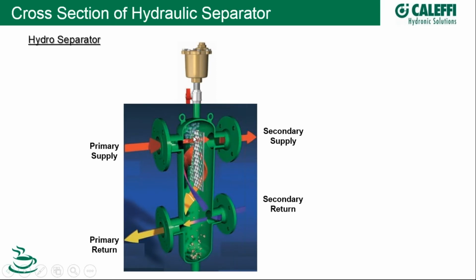Now these baffle plates have a little bit of perforation in them. You see these little holes perforated in them. This gives us a little bit of what's called coalescing, and you can see air bubbles that are actually coalescing out and up through the air vent. We'll talk more in detail about a dedicated coalescing separator in just a few slides. So and down below here, you see debris coming in off your secondary.